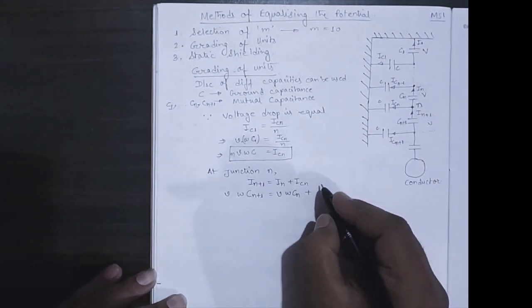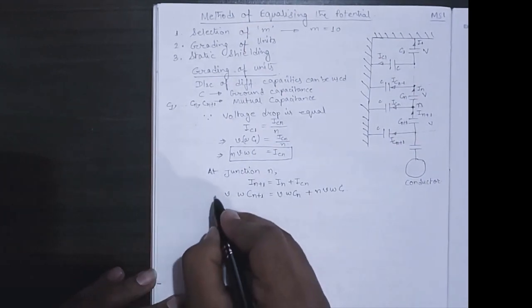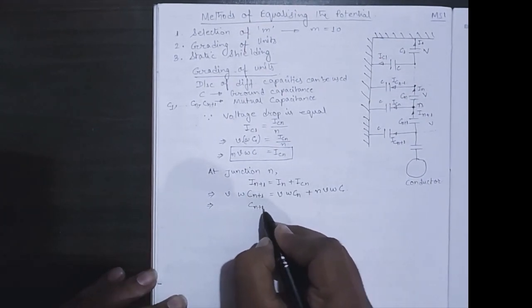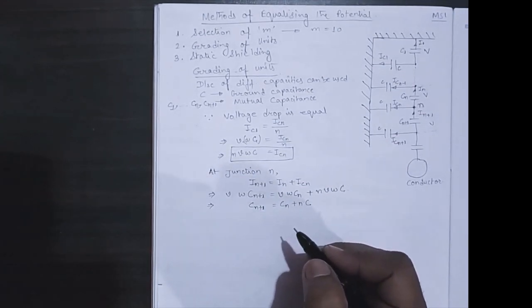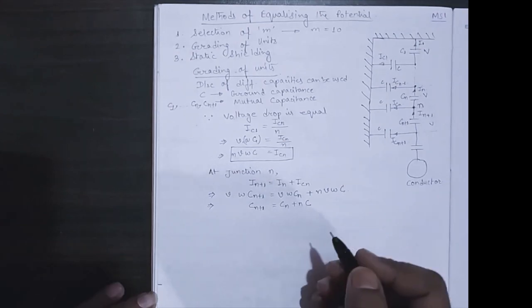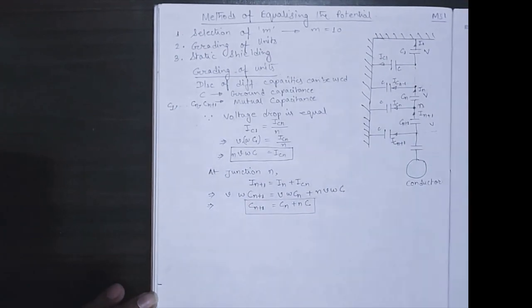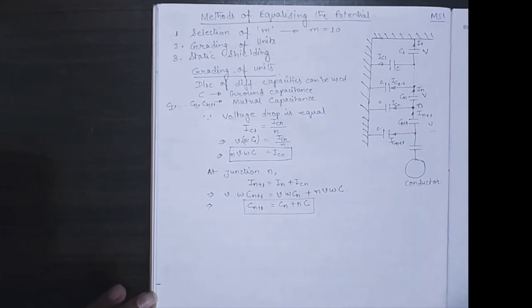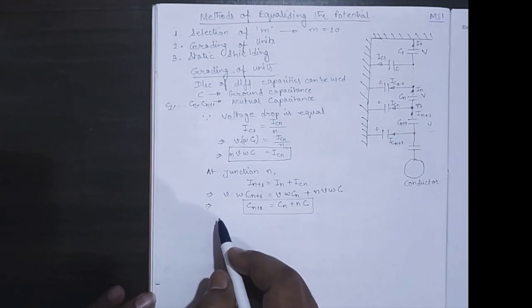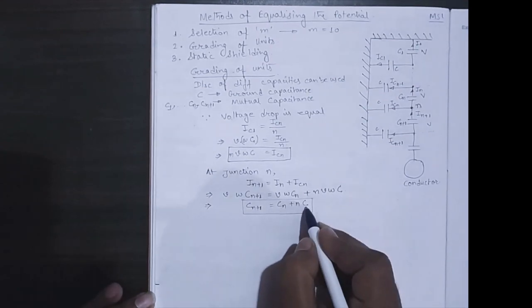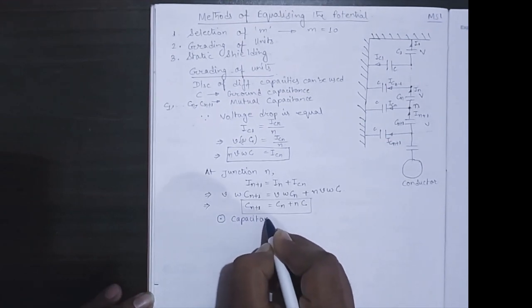And likewise voltage into impedance, sorry, voltage into reactance. No resistor is present, so voltage into reactance. So from here we are getting cn plus one equal to cn plus n c. This is important. From this you can understand that every capacitance below, that is going towards the conductor, is having more capacitance than the previous upper one.